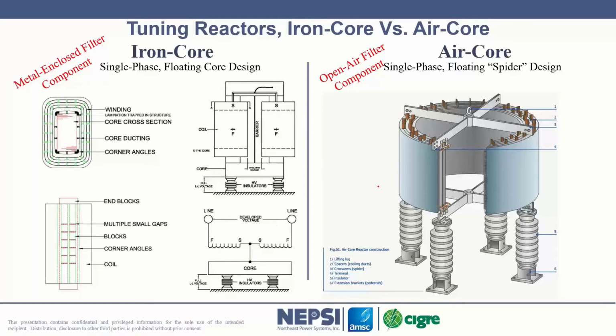In a sense, these designs are very similar. The only difference is air is being used here to create inductance, where here iron is being used to create inductance. The iron core supports the reactor winding here, and here you have aluminum webbing that supports the winding. The incoming winding is tacked to the webbing, and it's raised up in voltage. So you could call this a floating core or floating air core reactor. We have insulators on the bottom. Same concept is used here on the iron core reactor. It's the iron that helps to reduce the size and to encapsulate the magnetic field associated with the reactor.